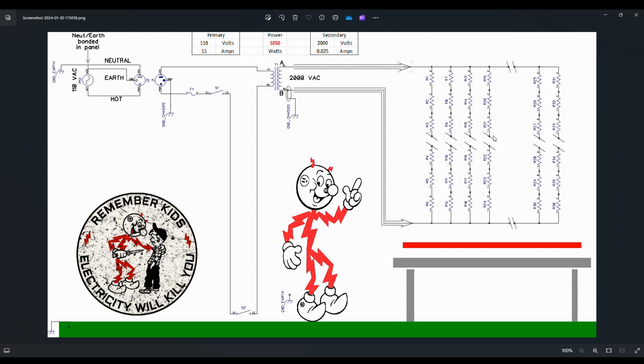If you found a piece of wood that was green under the right conditions, it would look like a very low resistance connection. I shouldn't say a dead short - it's not going to be like a piece of copper wire, but it could have resistance on the order of 1,000 ohms or less. Not 1 ohm or a fraction of an ohm, but close.